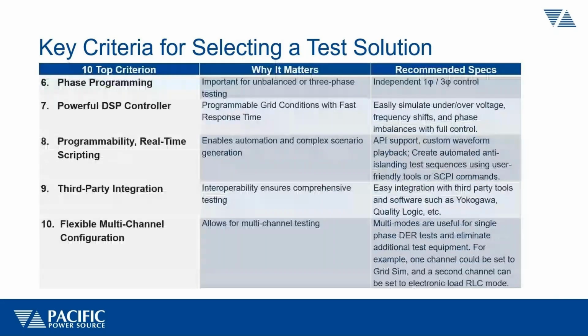Phase programming, obviously you want to do both single phase and three phase, and also be able to simulate unbalanced phase conditions to see if the inverters act accordingly and handle that properly. So you need fairly variable phase angle control. You need powerful controls on the power source, the grid simulator, to do immunity testing of voltage anomalies such as over and under voltage, frequency jumps and shifts, and phase imbalances. You want to be able to simulate all those for testing DERs as well.